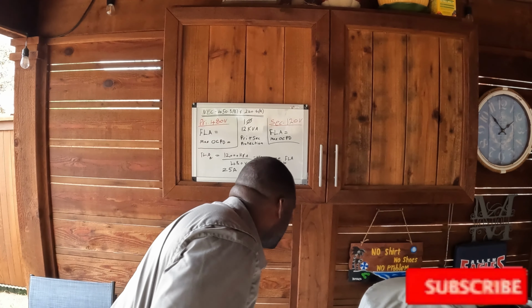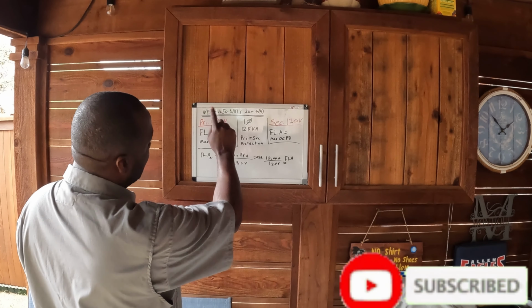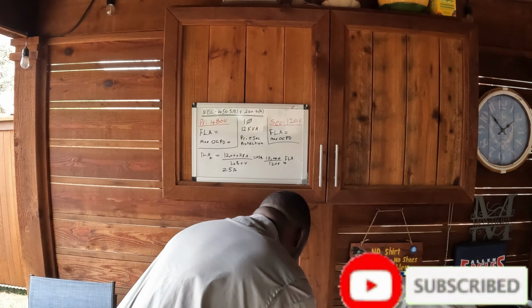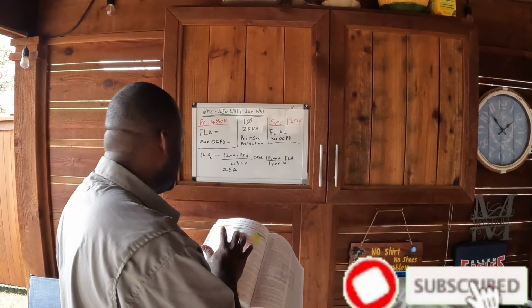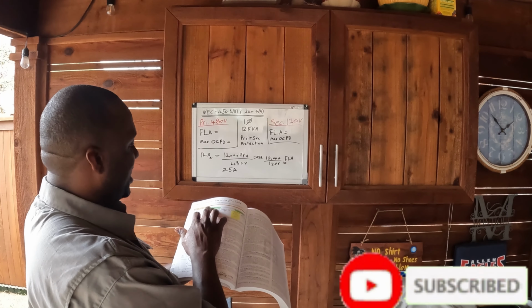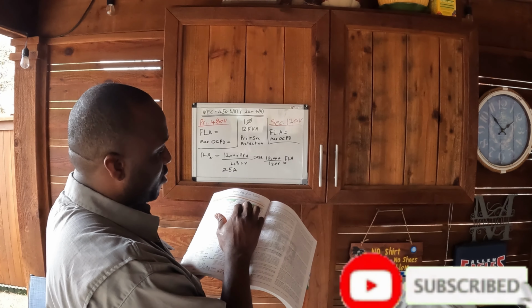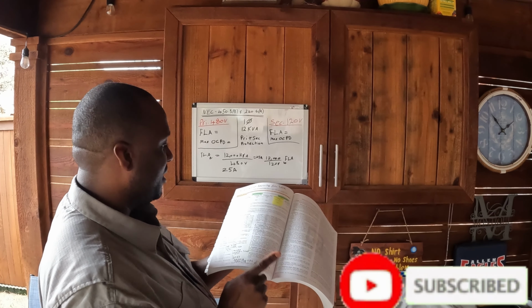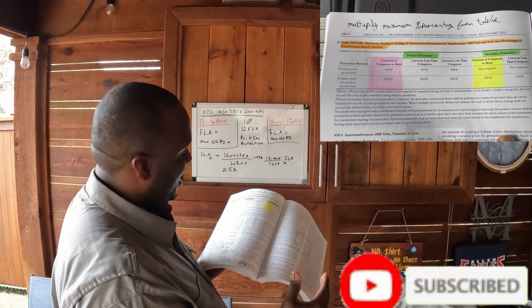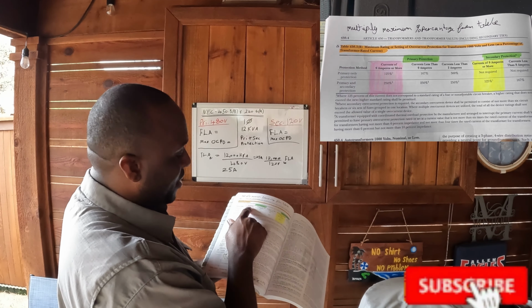Now, you're gonna go to the code book and look for this article right here, 450.3(B). And there we have the table. That's the maximum rating or setting of the overcurrent protective device for transformers 1000 volts or less. On that table it says primary and secondary, and we're dealing with the primary side right here. It says current of 9 amperes or more, so that's what we're looking for.